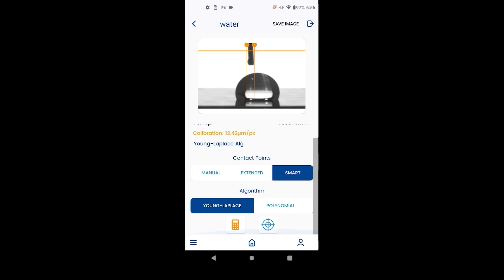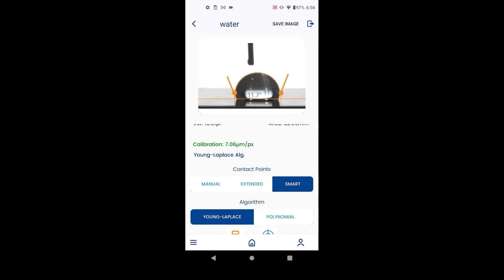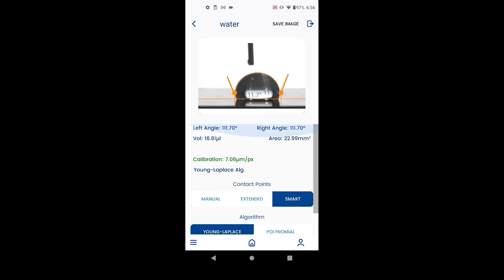If it's red or yellow then something is wrong and we suggest you recheck the diameter of the needle in the project screen and redo the calibration process. Generally, the lower the calibration number the better.